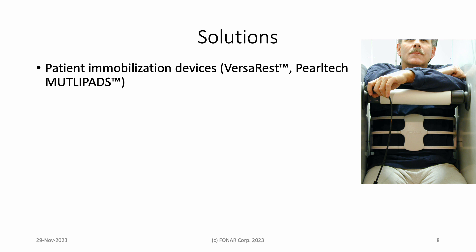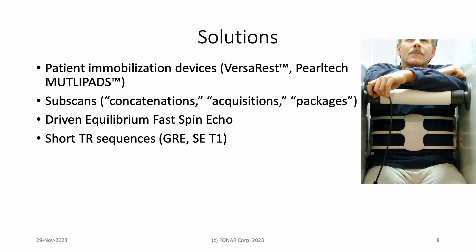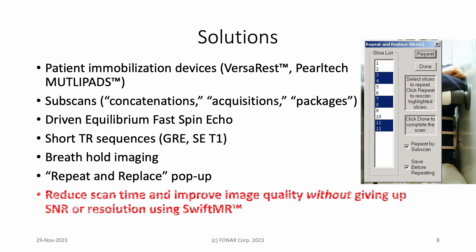We addressed the challenges in various ways. Here's a short list: We use patient immobilization devices, such as the VersaRest. We break up a scan into two or more sub-scans. We use driven equilibrium to preserve bright fluid signal in a fast spin echo sequence with a reduced repetition time TR. We work short TR gradient echo and spin echo sequences into clinical protocols. We use breath-hold imaging. One of our favorites on the FONAR scanner is repeat and replace, which avoids having to repeat all the slices in a scan that has sub-scans. Spoiler alert: thanks to AIRS Medical's finely tuned deep learning models, we now have a new tool at our disposal, one that improves image quality while enabling a reduction in scan time — SwiftMR.